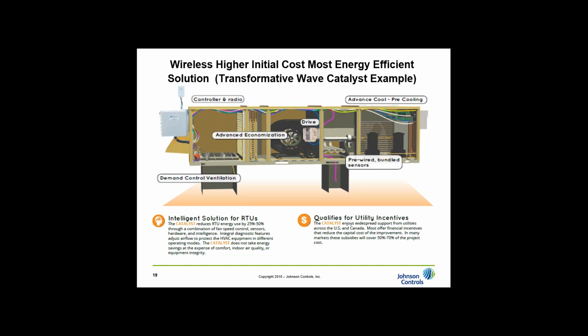Most of these systems contain advanced economization, which utilities offer rebates for. They're also wireless and report to central servers, giving you utility history from installation until you quit your software subscription, which is nominal, about $200 to $300 a year. Currently, rebates from PG&E are $155 a ton, which can add up quickly. For a 30-ton or 20-ton unit, you can get up to a $3,800 per unit maximum. Most of these systems have a payback of between 2 and 4 years, depending on the run hours of the facility. So it's a good way to control and lower your energy bill and cap your energy use moving forward.